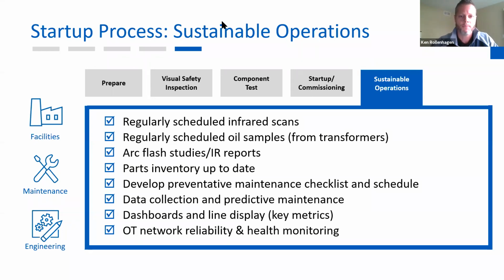Arc flash studies. We should be having arc flash studies done on a regular basis, 1 to 3 years. Anytime we have an addition on your building or extra equipment on your plant floor, really need to make an adjustment to your one-line diagram. Parts inventory, is that up to date? We spoke about this. Just as time goes on and maintenance is done on machines, there could be parts supplemented for others. Is your inventory up to date? What you're actually going to find on your plant floor, and then from some of these things, developing preventative maintenance checklist and a schedule. Having gone through tightening those terminals, it's all about preventing that downtime.